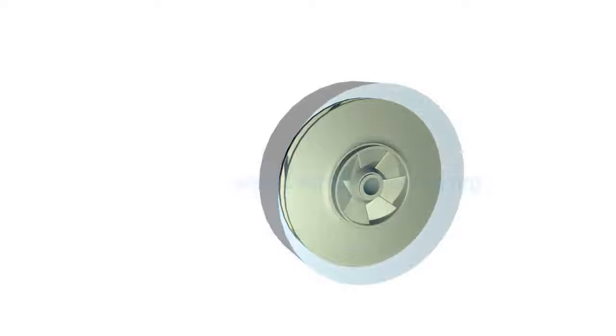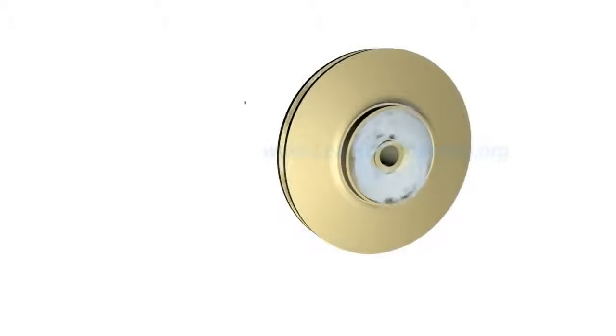The impeller is always immersed in water. When the impeller is made to rotate it makes the fluid surrounding it also rotate. This imparts centrifugal force to water particles and the water moves radially out. Since rotational mechanical energy is transferred to the fluid at discharge sides of impeller, both pressure and kinetic energy of water will rise.